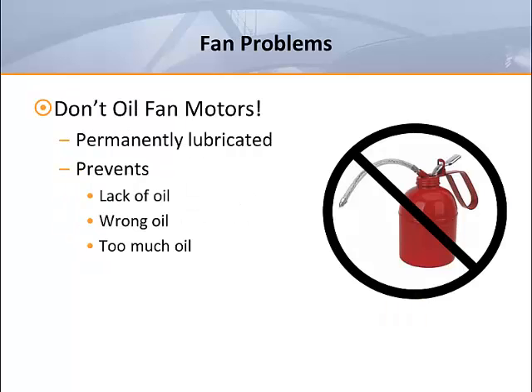Another problem involves oiling — put away those oil cans. At one time, motor manufacturers provided oiling ports and tubes and recommended periodic oiling. About 25 years ago, they eliminated the oiling tubes, capped the oiling ports, and no longer recommended oiling. All terminal unit motors used today are permanently lubricated and should require no oiling. The problem with motor oiling was that it either didn't get done at all, or the wrong oil was used, or too much oil was used. None of the terminal unit motors still in service today should ever need oiling.